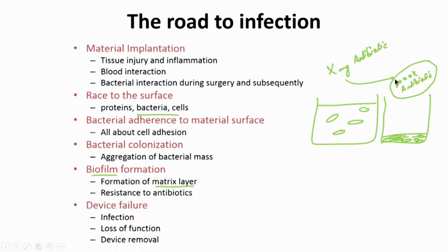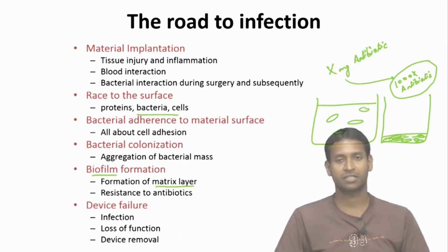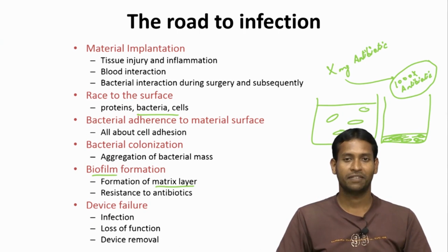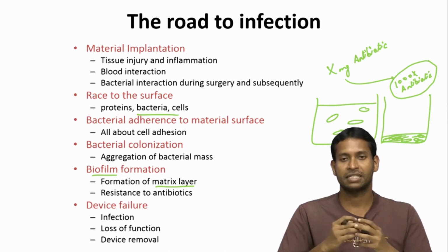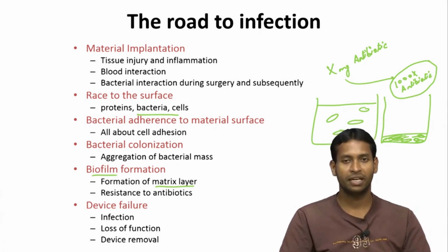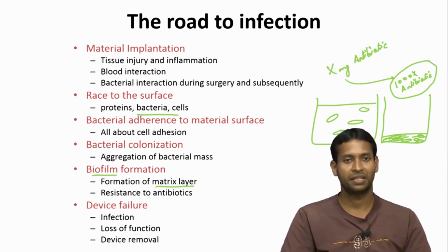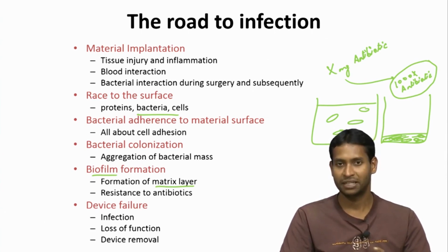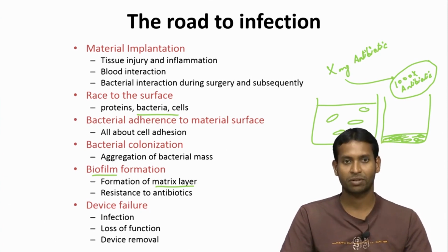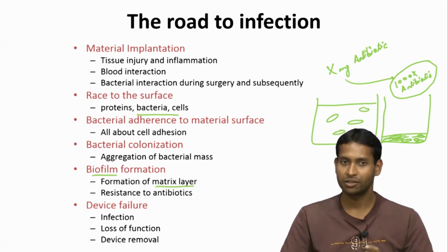And then once this biofilm is formed, ultimately the device fails. This could be due to several reasons. Maybe the device is there as a sensor, and then your sensing molecules are not able to reach their target site. We gave an example already of glucose, where we saw that glucose has difficulty permeating through this layer. It could be something else that is being sensed, maybe calcium ions, maybe the concentration of a drug, maybe the concentration of a solute. All of that leads to failure in sensing scenarios.